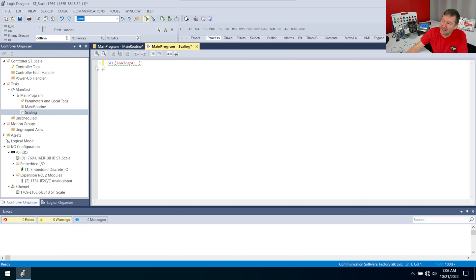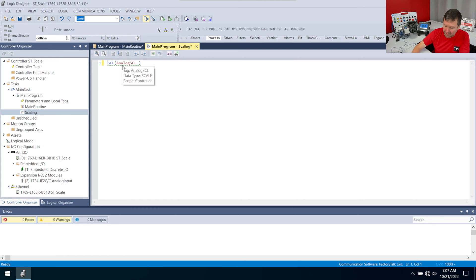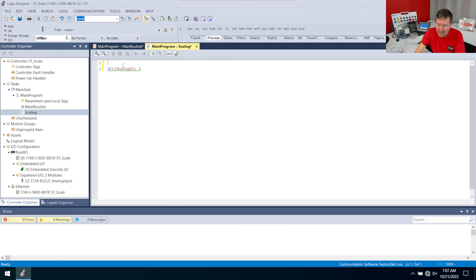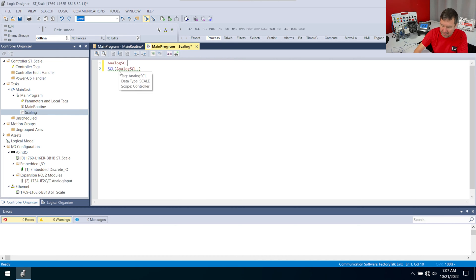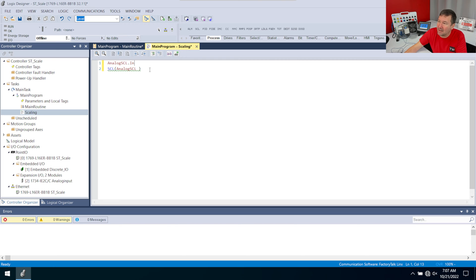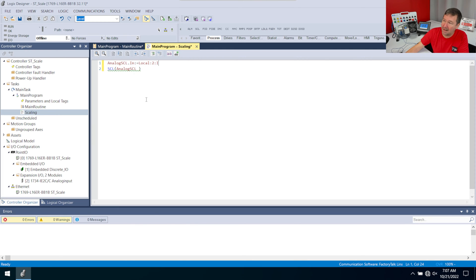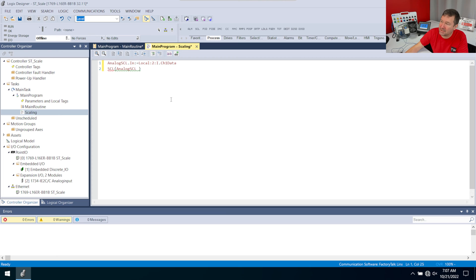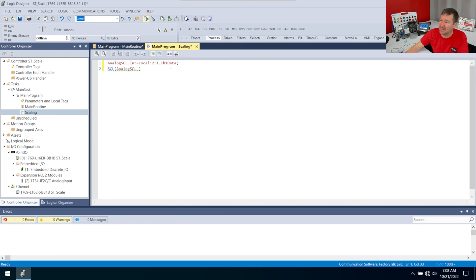Now, before I actually execute the SCL, I will need to put the analog input into that analog SCL. So I'm just going to hit enter and go up. I'm going to start typing analog SCL. And there it is. Dot. And we want this N right here. Colon equal. And then we're going to need this tag in my analog input. So it's going to start with local colon I dot. And then I want CH1 data because I have it wired to channel one. And I always forget these, but you need a semicolon at the end of that.